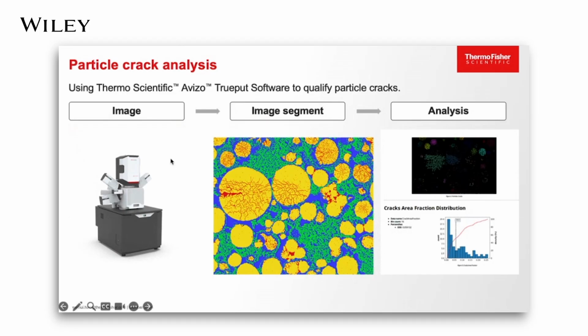We provide a system, as we mentioned on the last page, to make a non-site-specific cross-section with the mill and get the images of the cross-section quickly with the Apreo SEM. Also, we have a methodology to process the image and quantify how many cracks exist with Avizo TruePut software. This is a dedicated application built specifically for battery scientists and engineers to be able to do automated image interpretation. In the whole workflow, the SEM provides high-resolution images of the cross-section of the electrode, allowing visualization of particle cracks, and the image analysis software, Avizo TruePut, can be used to measure the size, distribution, and density of defects such as cracks.